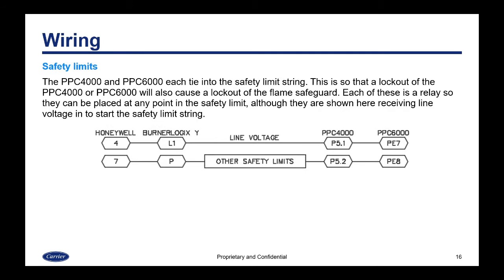The PPC4000 and 6000 each tie into the safety limit string as well, so that a lockout of the PPC4000 or 6000 will also cause a lockout of the flame safeguard. Each of these is a relay, so they can be placed at any point in the safety limit, and although in this diagram they are also shown receiving line voltage, to be at the beginning of the safety limit string.